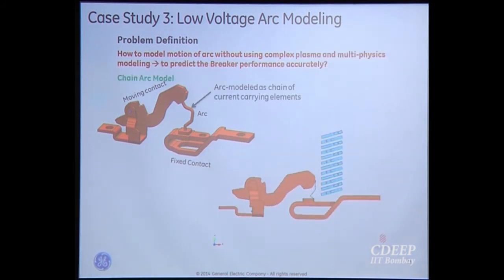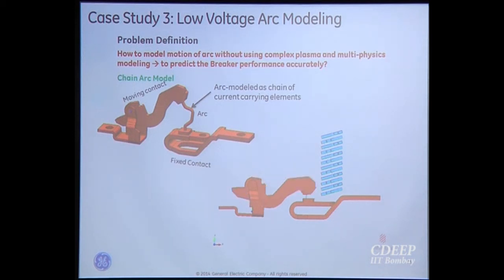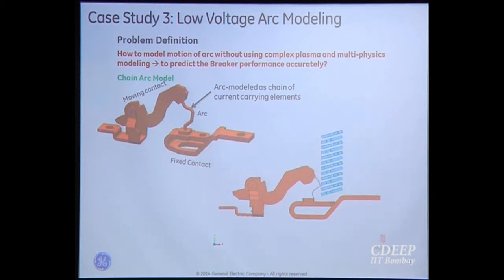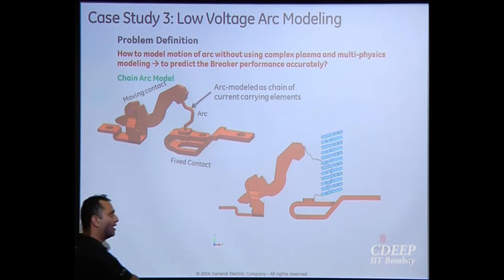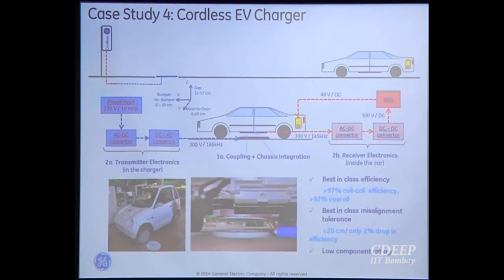Moving to circuit breakers: the arc comes in and gets split over the arc chutes. We model this and show some animation. Arc is typically modeled with CFD and plasma physics using multiple tools, but it takes a lot of time. If we are only interested in arc voltage and arc current and not temperature, we simply model the arc as a chain of small current-carrying elements that expand as the contact opens.